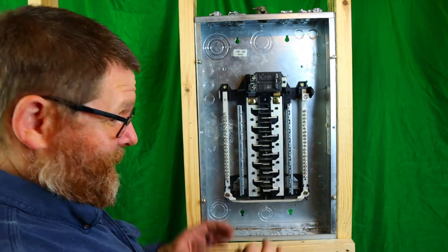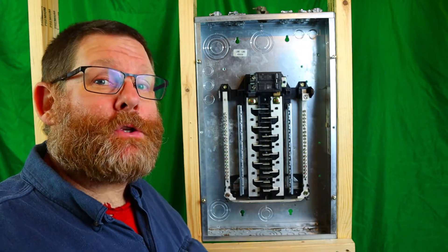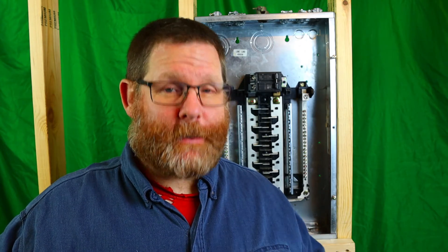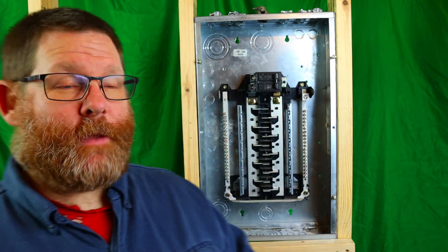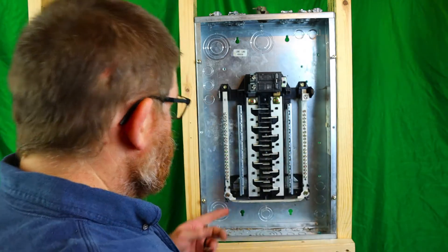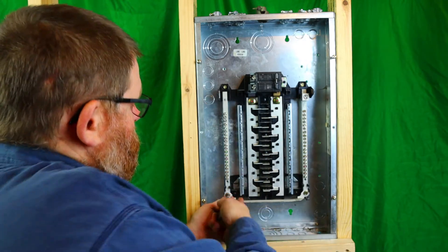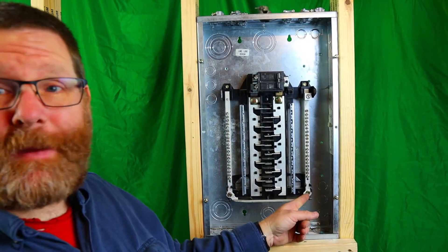But now for this, this is where it matters - you have to separate at your sub-panel. Now I'm going to show you how to do that right now. There's no green ground screw in there. You have to take this right here off, you have to remove that.